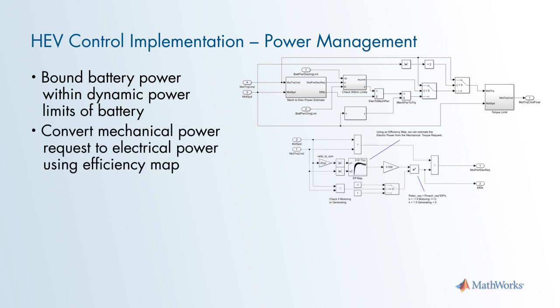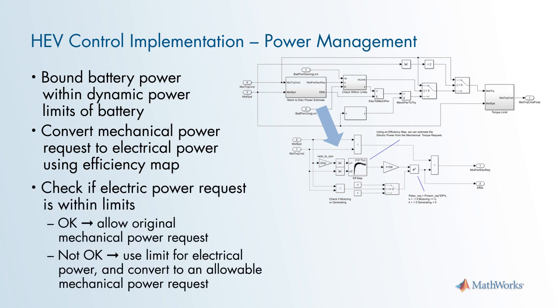This algorithm converts the mechanical torque request to a power request, then calculates the electrical power request using an efficiency map. It checks if the electric power request is within the dynamic BMS power limits. If it is within the limit, it will allow the original mechanical power request through. If the limit is exceeded, it uses the upper limit for the electrical power request and converts to an allowable mechanical power and torque request using the efficiency map.